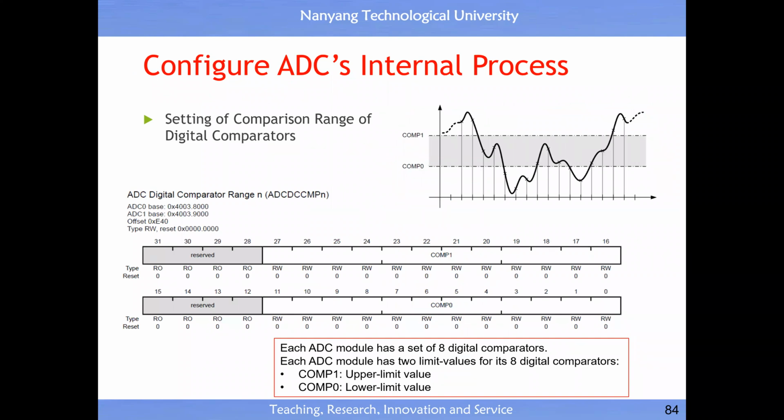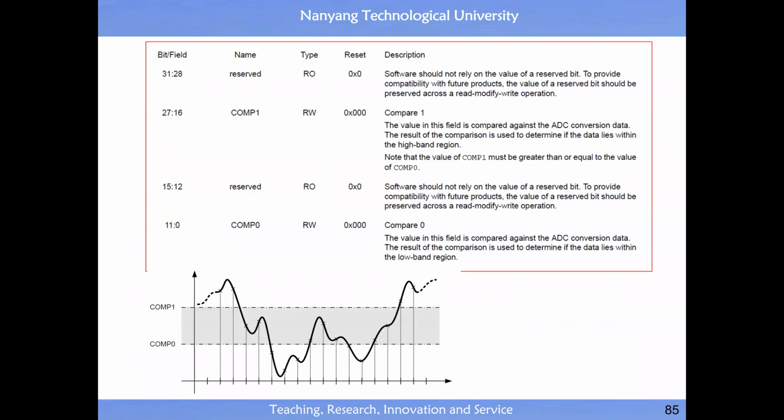Okay, this one is for process control. You can set the upper limit, lower limit, because the output can go to the comparator. Comparator has upper limit, lower limit. Then the hardware will trigger an alarm if the actual value exceeds the upper limit or goes below the lower limit. So this is needed in the production line. Then for you, if let's say you don't care about this, then ignore it. Okay. So again, you see, you have a sport car. Also, you want to ride a bicycle. All right. So that is the situation. You pay the price of a bicycle, you get the sport car.